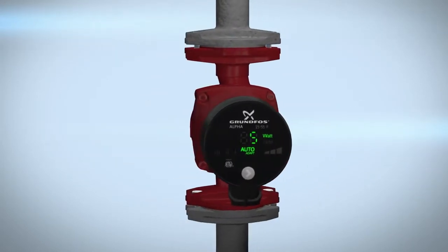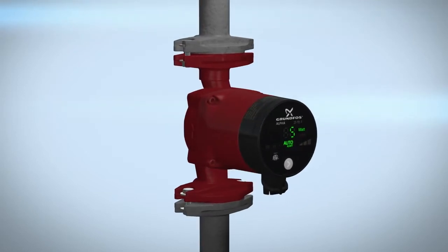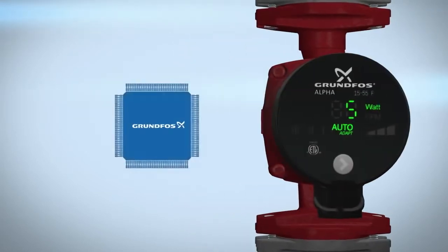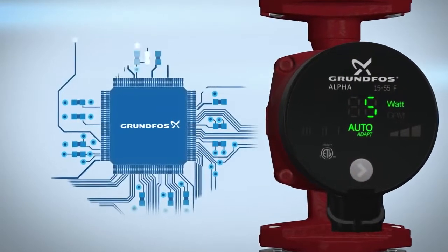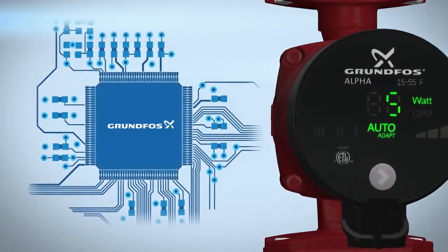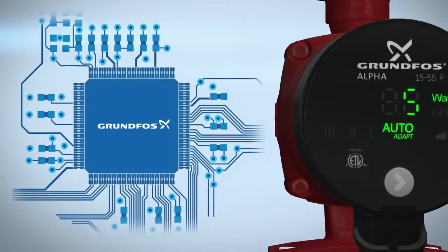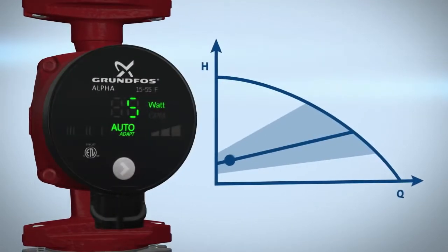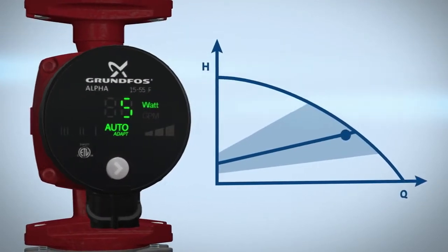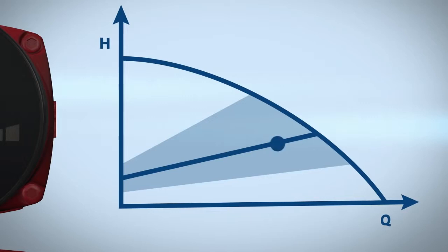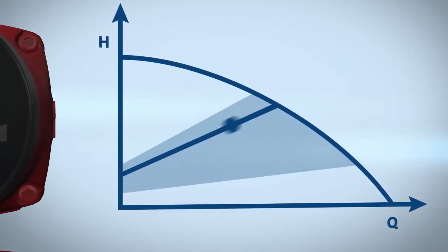Alpha uses an internal control processor to measure the change in system pressure, typically caused by opening or closing valves. This control functionality means AutoAdapt's set point is dynamic and is based on actual demand changes in the operating system.